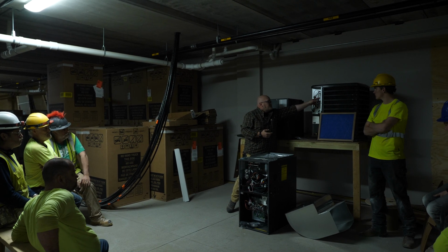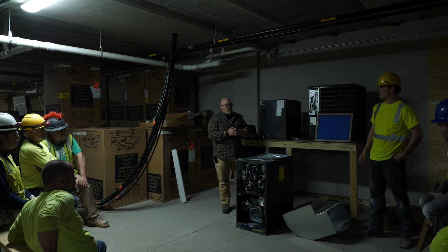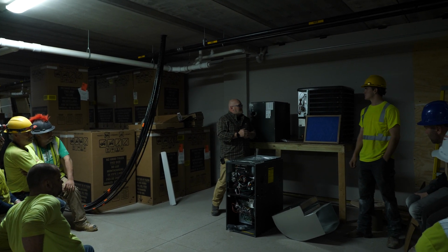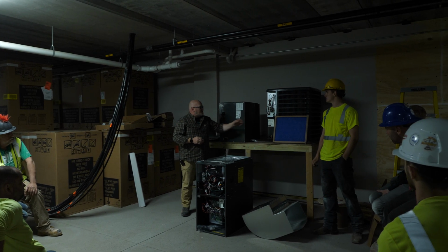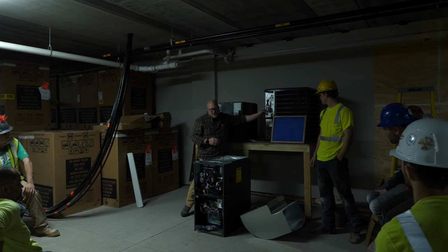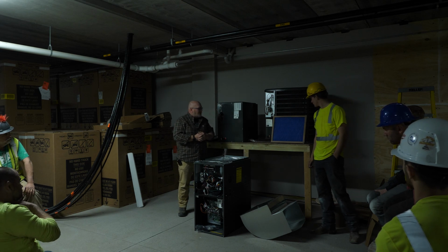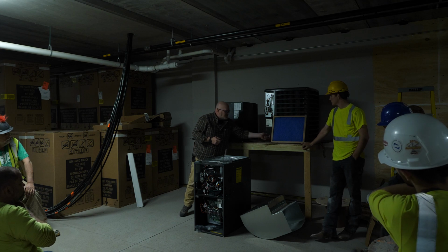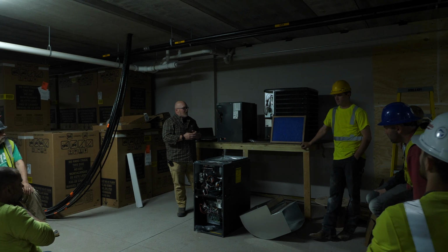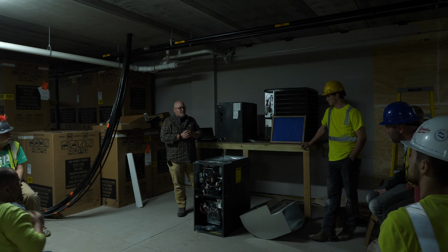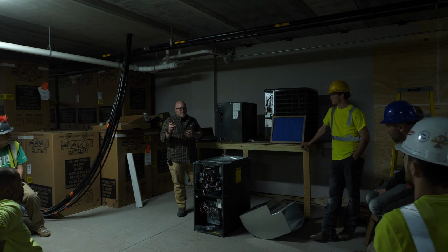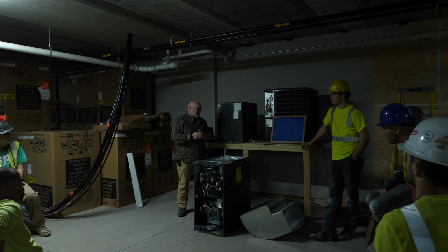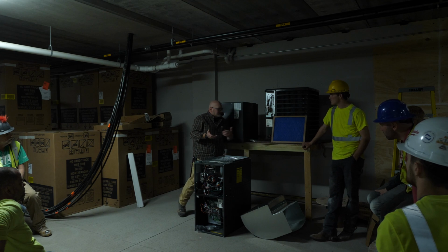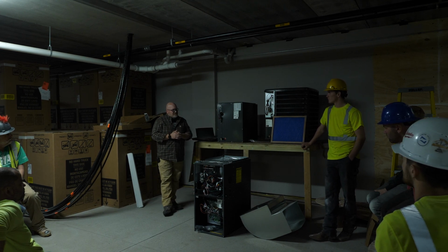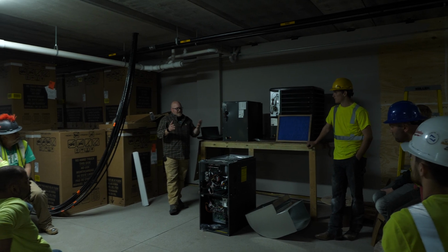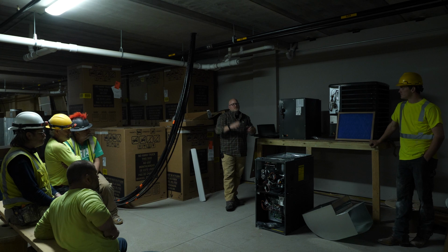So you could either have a capacitor that's blown and it's swelled up real big. Replace that. Most likely your condenser fan is going to go back and start running. We talked about the contactor. The contactor that's chattering, that's time for a replacement on the contactor. And we also talked about the suction line set here that goes in, whether it has frost built up on it or whether it's warm. And ideally, on an R22 system, we want to feel for that beer can cold. On the 410A system, it's going to be not as cold, usually looking at return temperatures at about maybe 50, 60 degrees. So with that being said, just a couple of things that you can look at in your system.